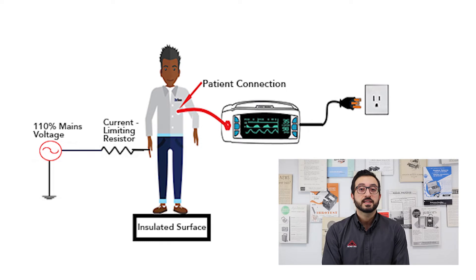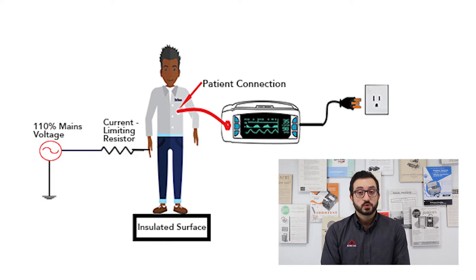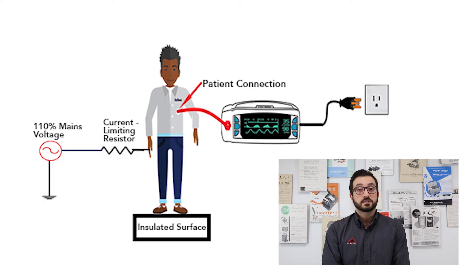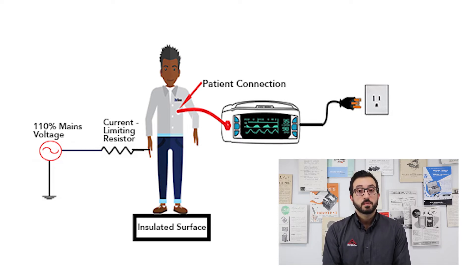The mains and applied part leakage current tests can be viewed as slightly more stringent compared to the other types of leakage current tests, and it is required for class 1 or class 2 medical devices that incorporate applied parts that may fall under the category of either F type or CF type.